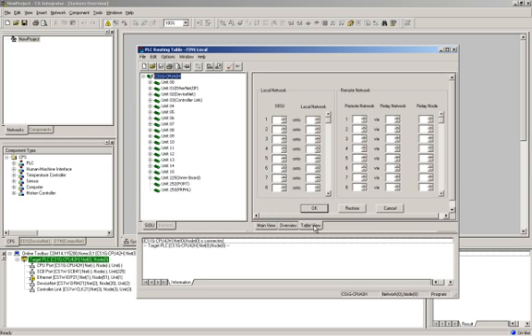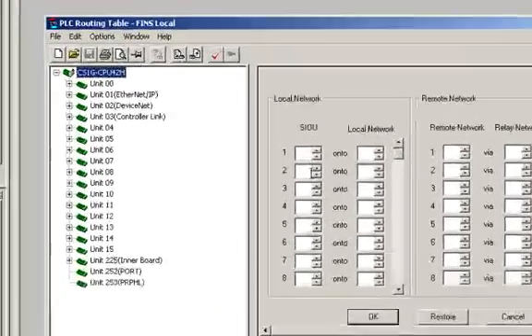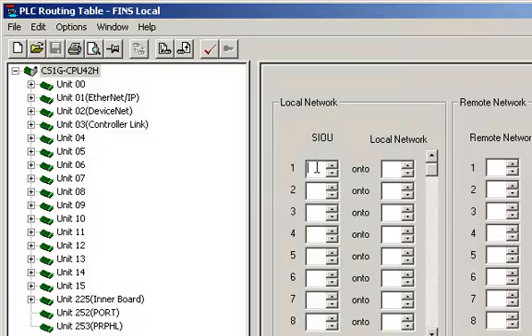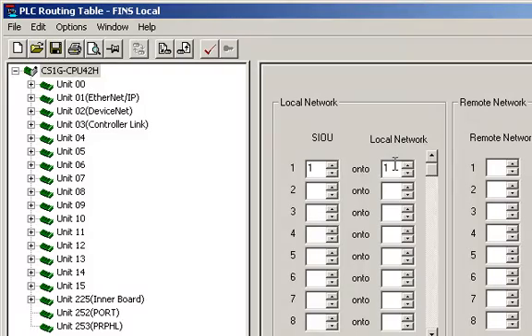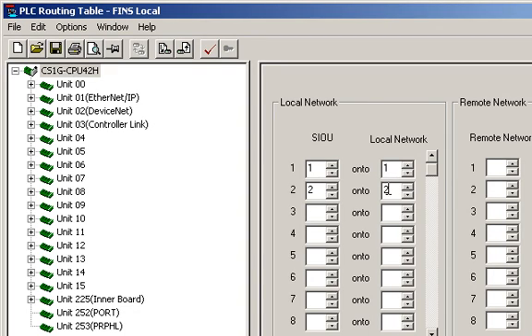In the Table View, there is a simple interface for assigning the unit number, also called the SIOU on the left, and the FINS network number on the right. For my three network modules and corresponding FINS network numbers, I will enter unit number one and assign to it FINS network number one. I will enter unit number two and assign to it FINS network number two and assign unit number three FINS network number three.